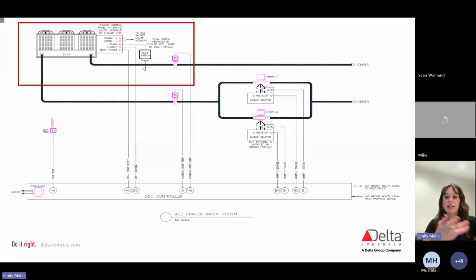So also here you might see Ethernet, you might see IP, depends on how it's talking. It's just in this schematic, it's BACnet MSTP. And again, this is normally provided by the chiller manufacturer themselves. The next component on there is going to be a flow switch, also manufactured by the chiller manufacturer, but typically it's going to be wired up by the engineer. And next, we're continuing to move towards the right there. Sorry, this goes a lot better in person, so I can point to that diagram for you guys.